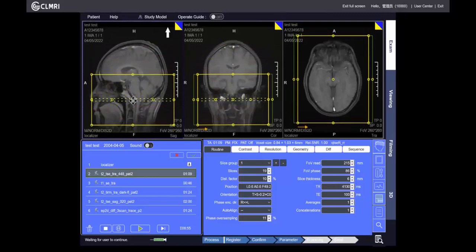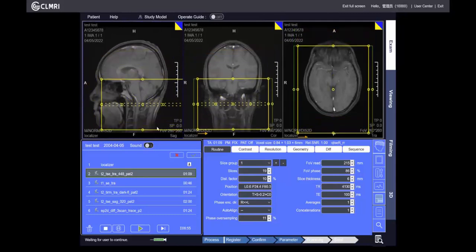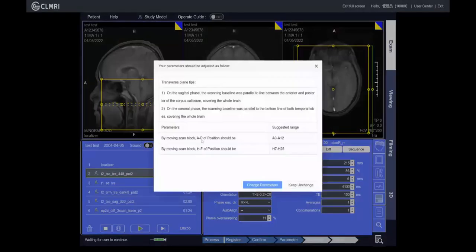We provide a tips system. If your scan plan is not correct, when you click the tick button, the system will give you tips to show how to operate the software correctly and show the parameter ranges — the right parameters should be adjusted to the right range. You can choose to change the parameters or keep them unchanged.